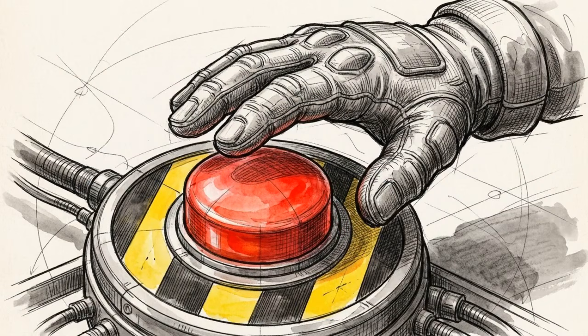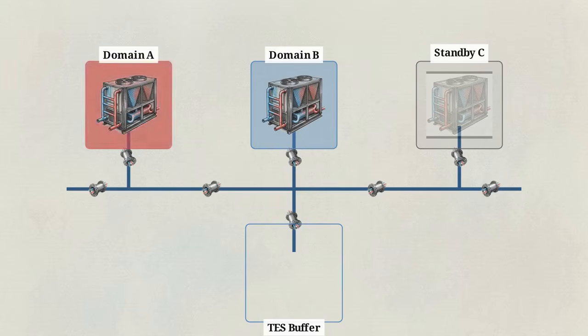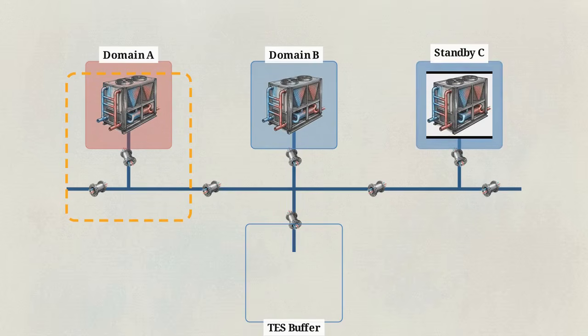Consider a scenario where a primary chiller faults upon receiving power and completely fails to restart. The unbending operational rule here is to never force an override on original equipment manufacturer safeties. The correct protocol is to isolate that specific chiller domain, immediately start the standby train, and rely on the thermal energy storage buffer to buy the necessary time.